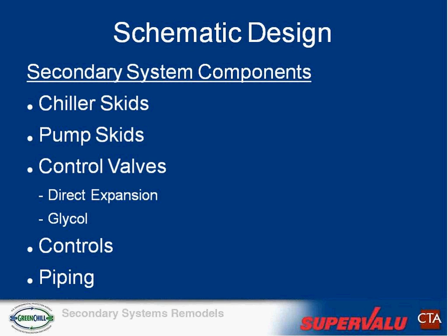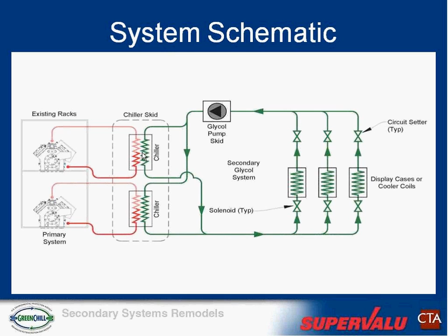Here's a schematic of the first picture I showed you, where we had single compressors tied in, with a chiller skid where we pipe the DX system and tie it to the hydronic system, and then a pump skid that would pump glycol to these chillers in parallel, and then out to the display cases or cooler coils.